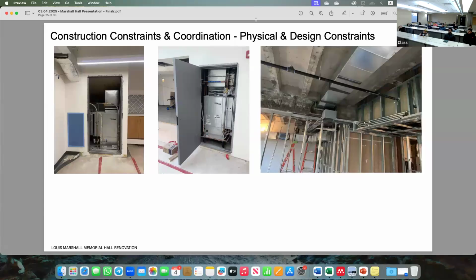What we also learned in the submittal process is that units over a certain size have a water side economizer, which no one knew about. So most of our units actually came in about a foot larger than they'd been designed for, even in our coordination drawings, because the manufacturer didn't tell the contractor until everything was ordered. So we had a lot of things to work with.